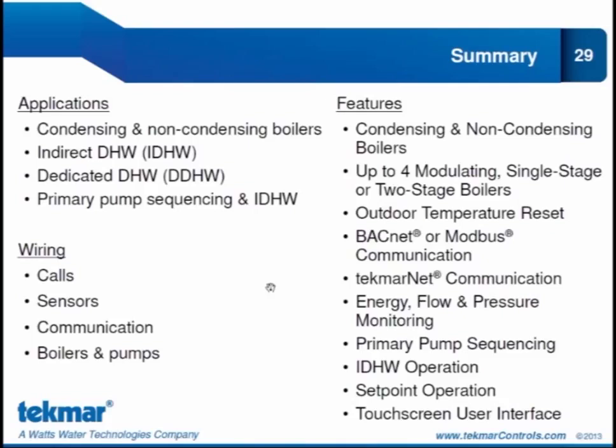Again, we looked at the Setpoint Operation and how we can receive a Setpoint call from either a contact closure, how we can receive a Setpoint call from communication from a tekmarNet for Setpoint control, like a 161 or 162, or how we can receive that Setpoint call from a building automation system. And we also talked about the touchscreen user interface and how it's very easy to navigate the menus. We can use the next and the back item buttons so that if we skip an item or want to revisit an item, we don't have to scroll through all of them. We also saw how this control displays the boiler output so that we can see at a glance how our system is operating.